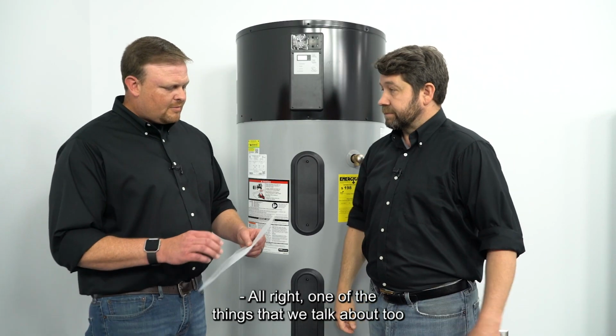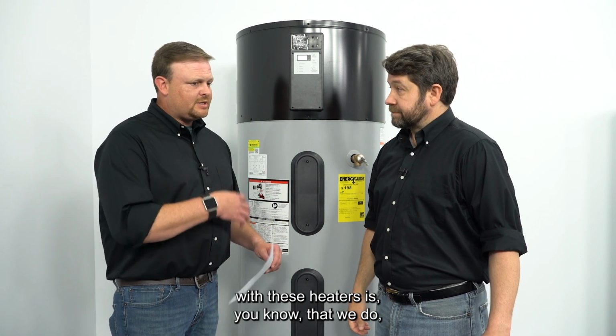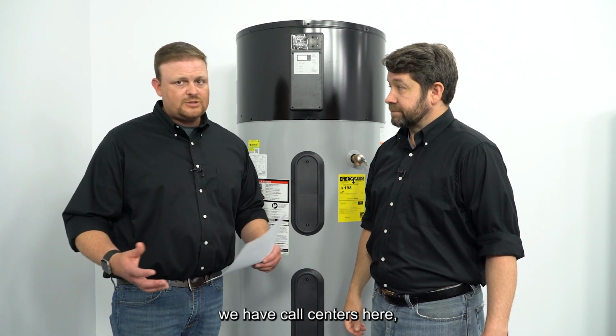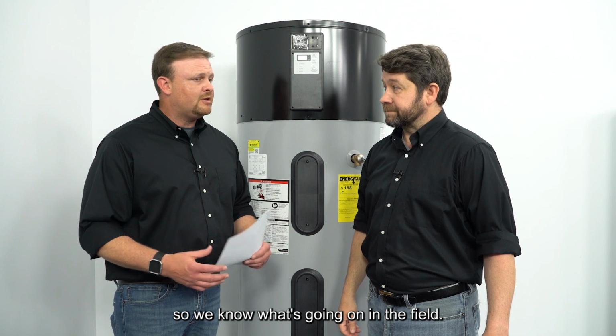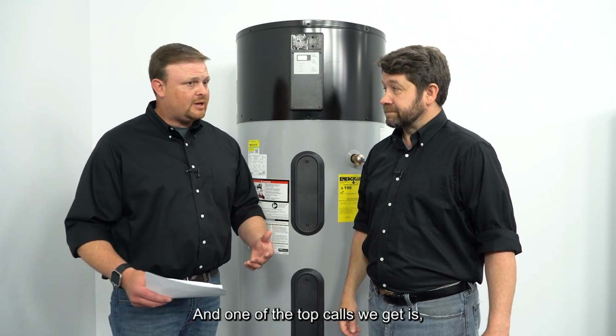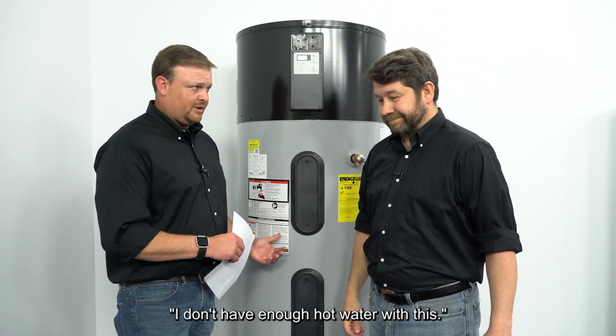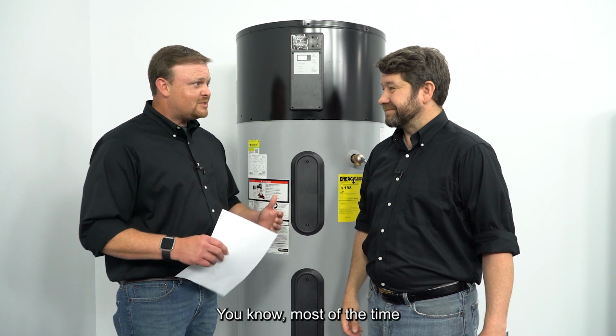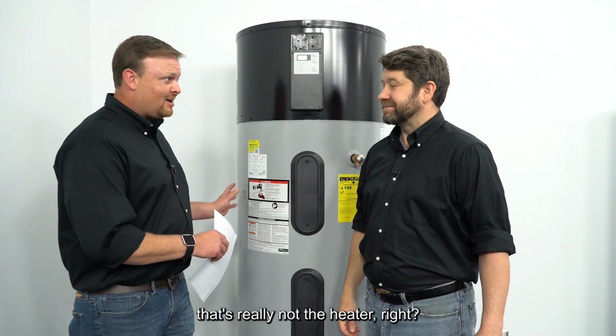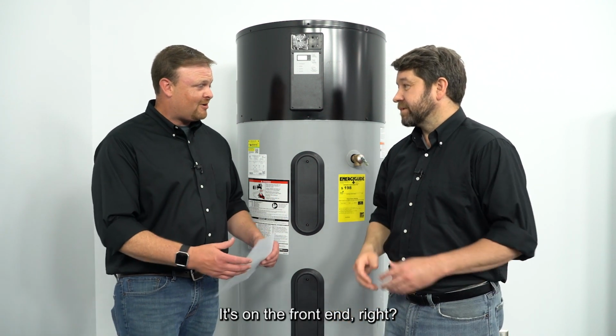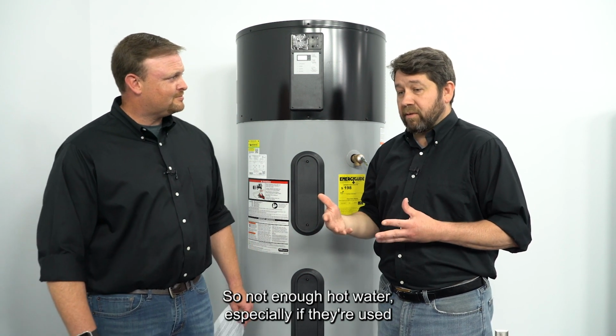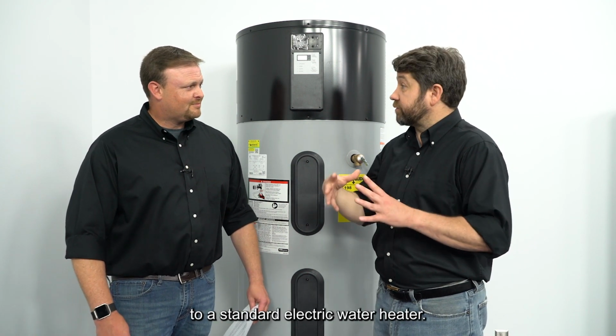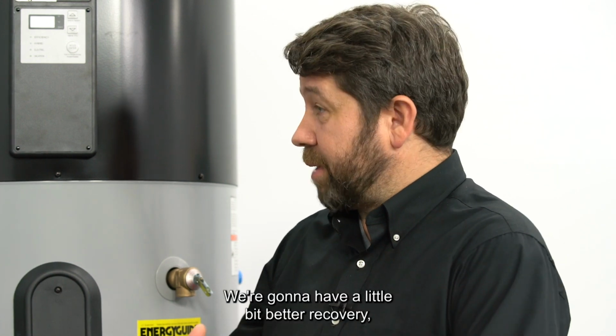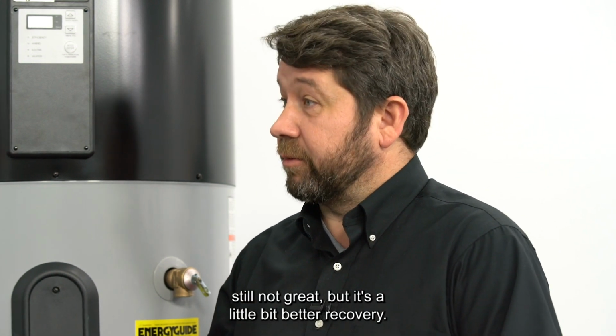One of the things that we talk about with these heaters is, we have call centers here, so we know what's going on in the field. And one of the top calls we get is, I don't have enough hot water with this. Most of the time, that's really not the heater. It's on the front end, so not enough hot water, especially if they're used to a standard electric water heater. We're going to have a little bit better recovery. Still not great, but it's a little bit better recovery.